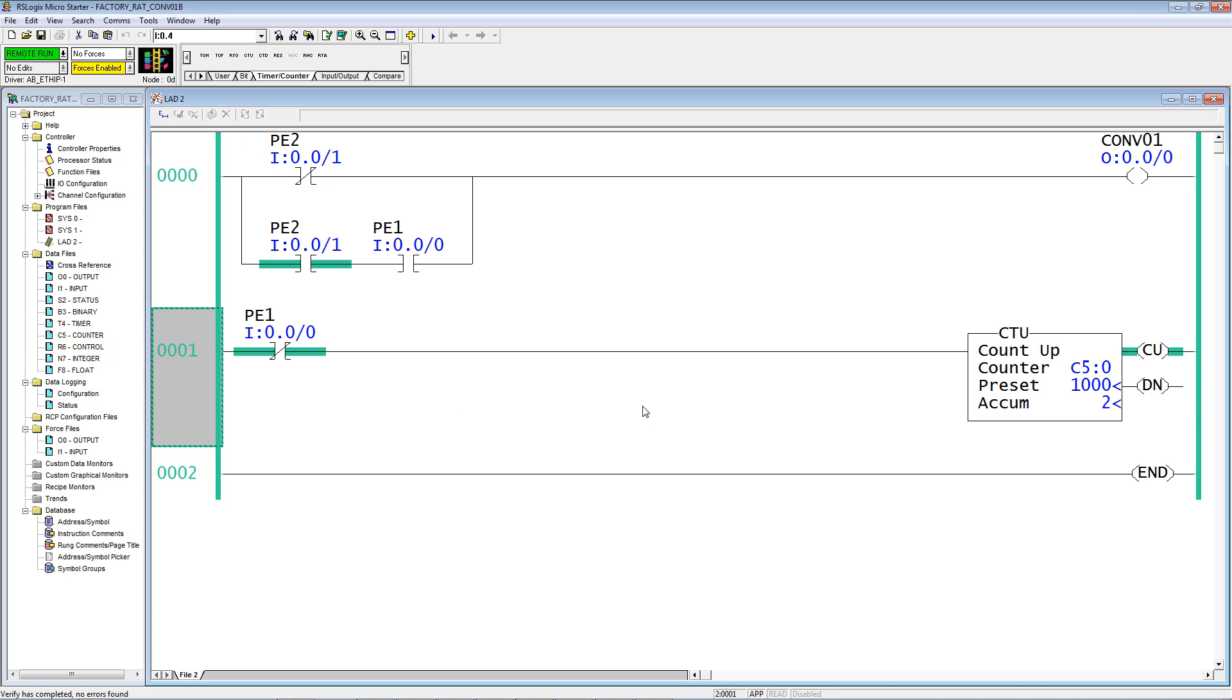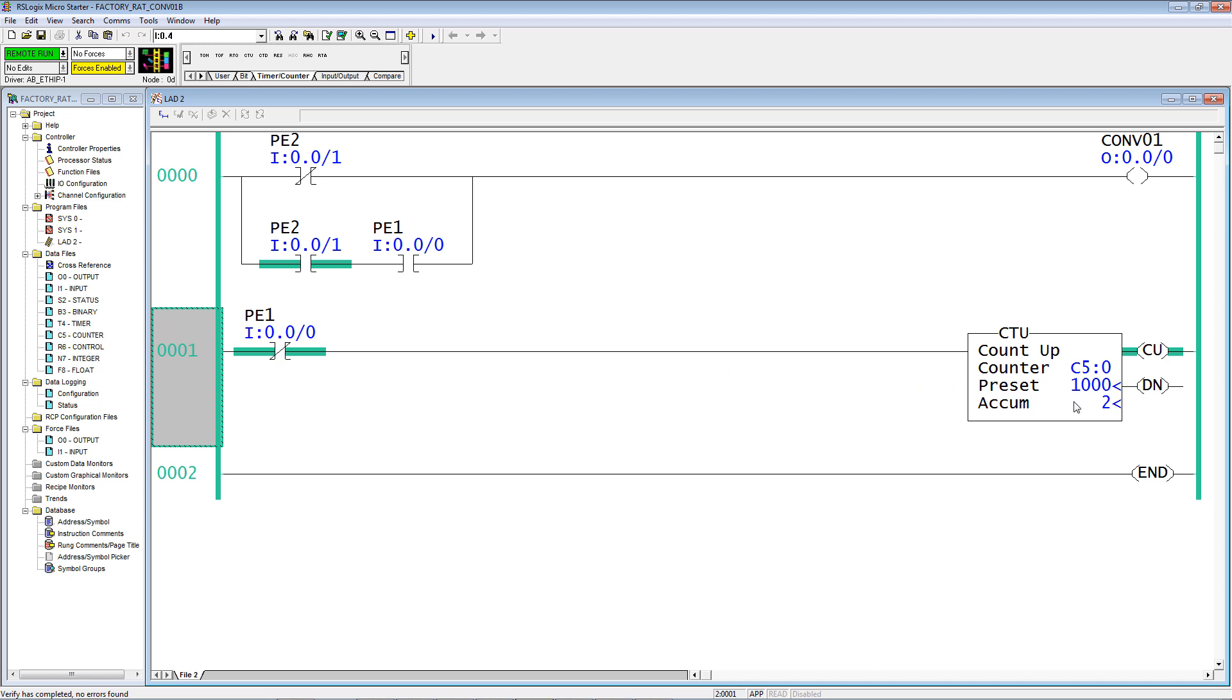You probably noticed here that the count is now two, and this is a drawback of the counter instructions. Because I was editing the rung and this was false, when I went to true if off and finalized it, it went from false to true and it incremented once. You always have to be aware of that behavior.